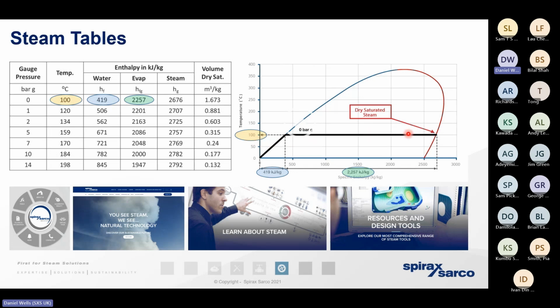So the overall aim of steam generation is to ensure that the steam exists on the dry saturated steam line, or as close to the dry saturated steam line as is possible. If we don't have dry saturated steam, if the steam sits in the wet steam zone here, then we're likely to encounter those issues that we discussed in some detail last week. We're likely to encounter more erosion, more corrosion, and more water hammer in the infrastructure.